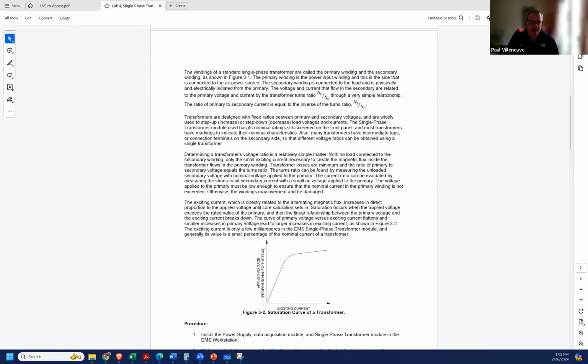You'll notice that the applied voltage, or better said, the open circuit or secondary voltage, is going to be proportional to the excitation current. But because of saturation, it's not directly proportional, because when we get to this point in our curve, that's the knee point, where it starts to peel off from being linear to nonlinear.